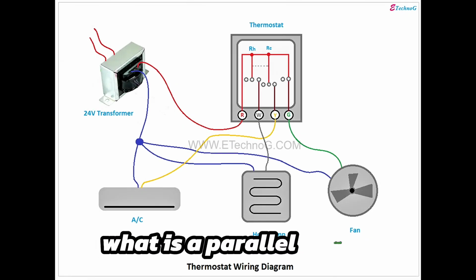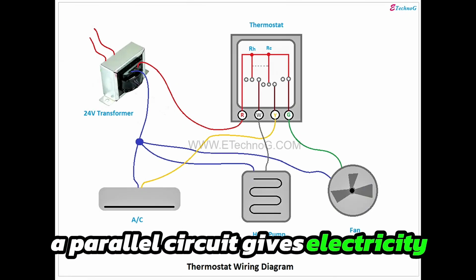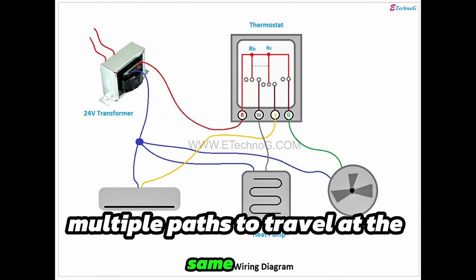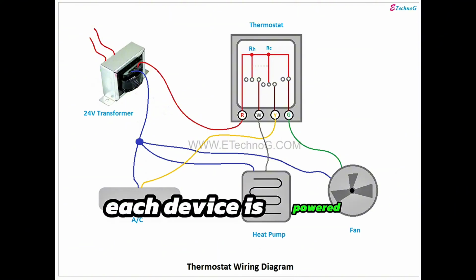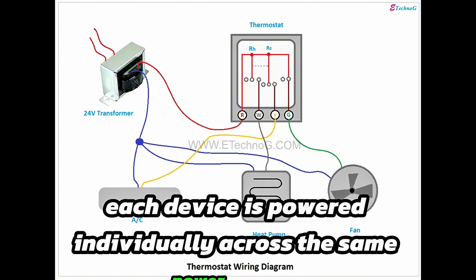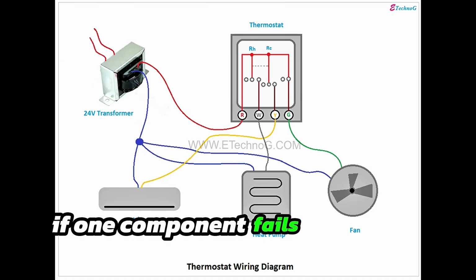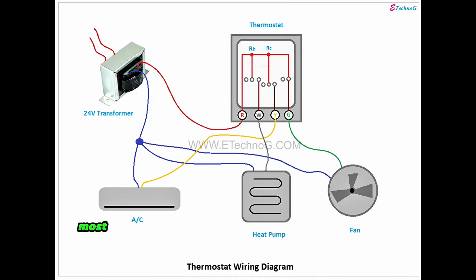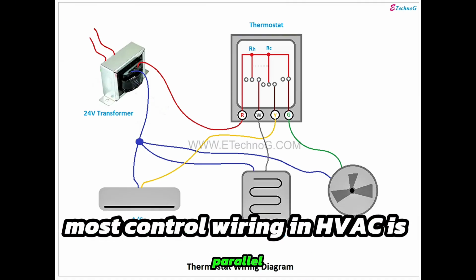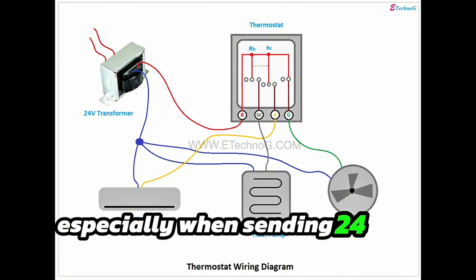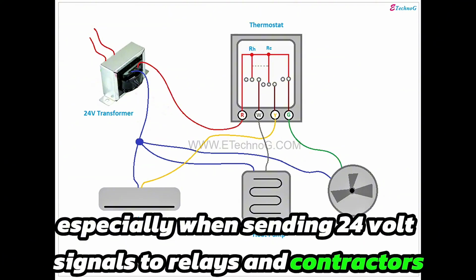What is a parallel circuit? A parallel circuit gives electricity multiple paths to travel at the same time. Each device is powered individually across the same power source. If one component fails, the others keep working. Most control wiring in HVAC is parallel, especially when sending 24-volt signals to relays and contactors.